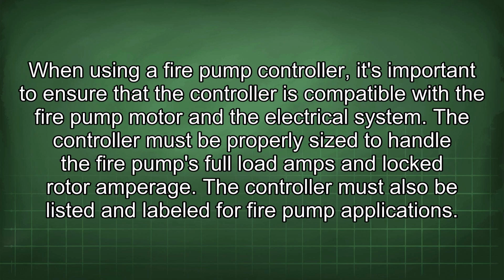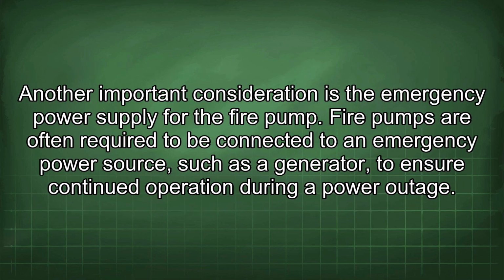When using a fire pump controller, it's important to ensure that the controller is compatible with the fire pump motor and the electrical system. The controller must be properly sized to handle the fire pump's full load amps and locked rotor amperage. The controller must also be listed and labeled for fire pump applications. Another important consideration is the emergency power supply for the fire pump.